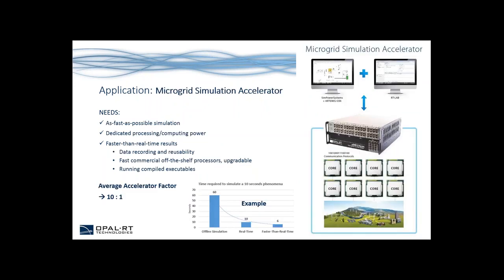The fourth application is our microgrid simulation accelerator. In this case, we're not necessarily talking about real-time simulation, but faster-than-real-time simulation. We want as fast a simulation as possible, requiring dedicated processing and computing power. We want faster-than-real-time results with data recording, using fast commercial off-the-shelf products that are easily upgradable, with objectives to run compiled executables. Based on our experience, we have seen an average acceleration factor of 10 to 1 — meaning, for example, if a 10-second phenomenon takes 60 seconds offline, it would take 10 seconds in real-time and could be achieved in about 6 seconds in faster-than-real-time.